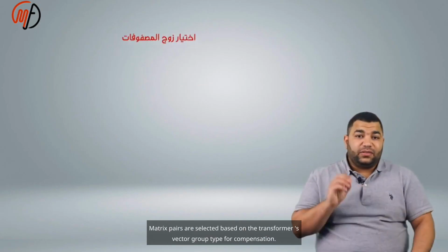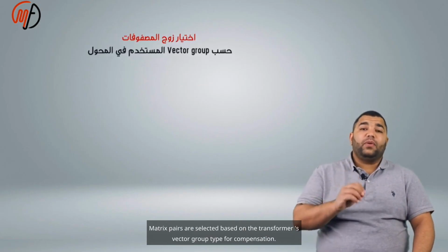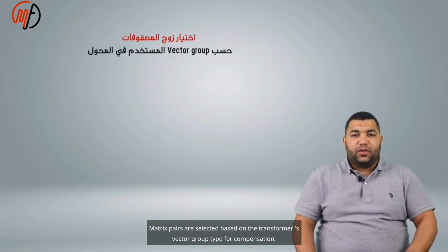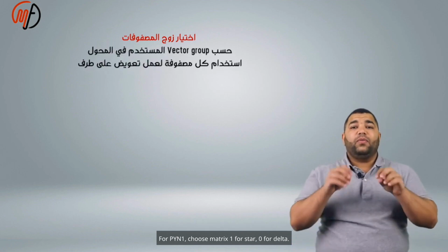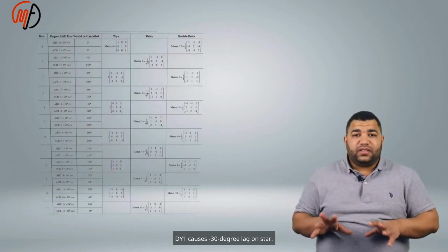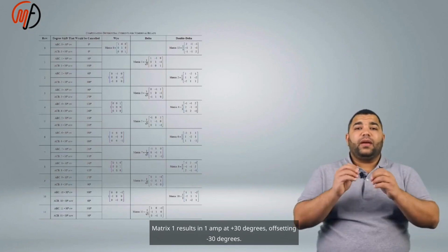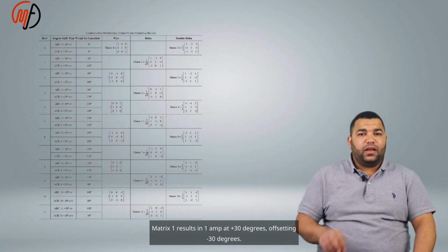Matrix pairs are selected based on the transformer's vector group type for compensation. For DYN1, choose matrix 1 for star, 0 for delta. DY1 causes 30-degree lag on star. Matrix 1 results in 1 amp at plus 30 degrees, offsetting 30 degrees.